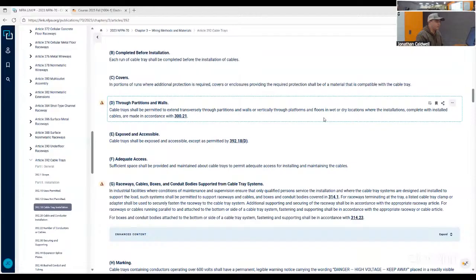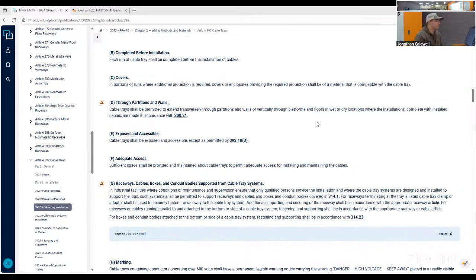If you're in a brand new building or commercial building, make sure the raceway is completed. It's not that hard. Even out at Simplot, we are doing a brand new building out there and the raceways will be completed before we start running the cable. That includes the conduit drops down from the tray.